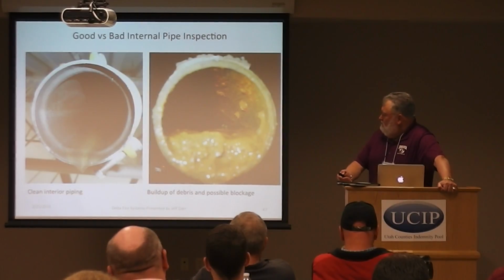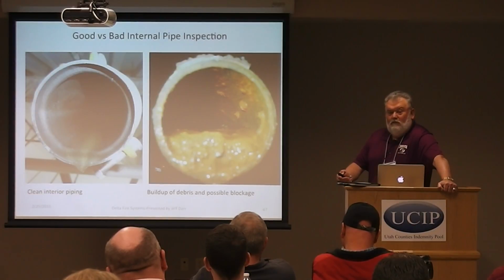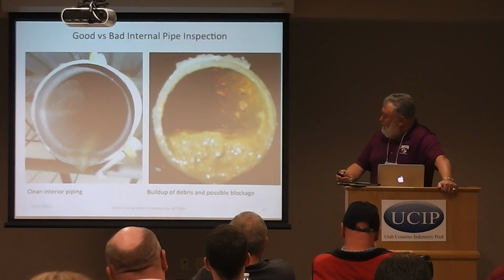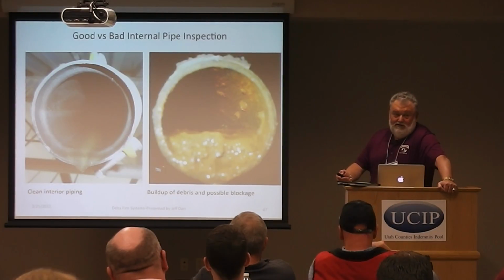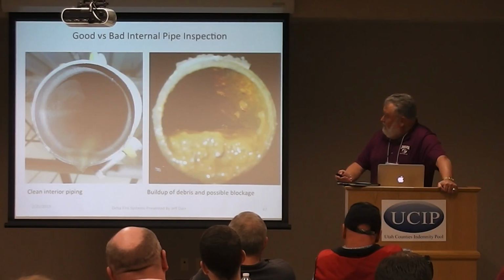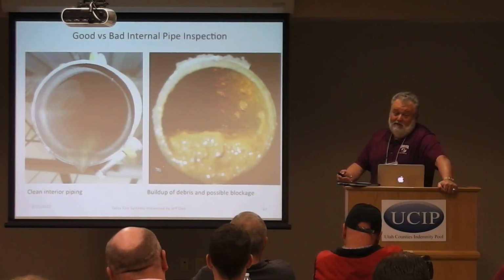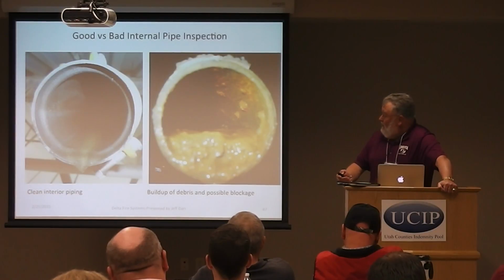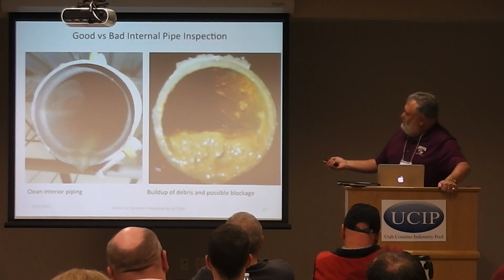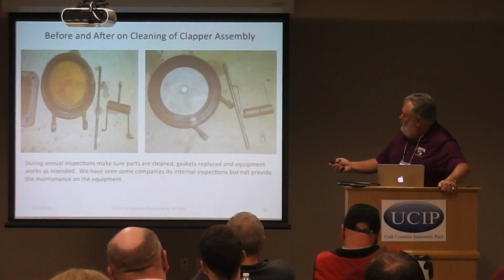I wanted to show you some examples of what we find, good and bad, when we pull the flushing connections off of some systems. You can see the system on the right obviously is plugged up with stuff. The one on the left was actually installed before the one on the right, but it's been maintained properly and it still looks in good shape.